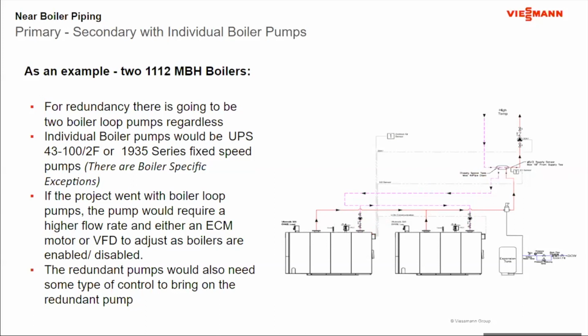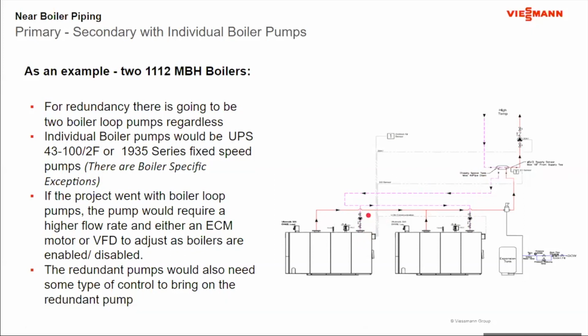And so again, just as with the isolation valves, when the boiler is enabled, the enabled boiler starts its pump and flow, and then it will flow water through the boiler itself. Now, the advantage of doing this versus the other install is, first off, the pumps are only sized for the flow rate of the individual boiler. So when I do a single boiler pump, that single boiler pump has to be sized based on the flow rate through all of the boilers. So it tends to be a much bigger pump, okay?